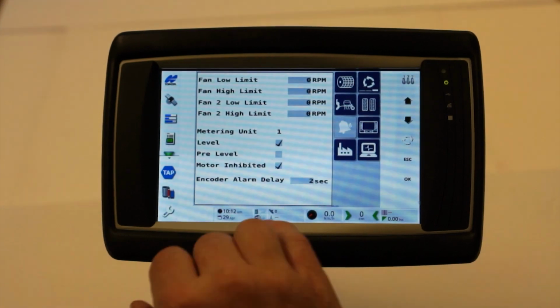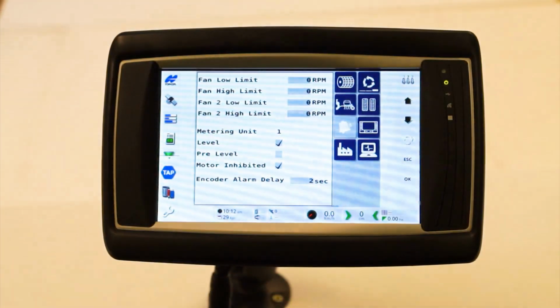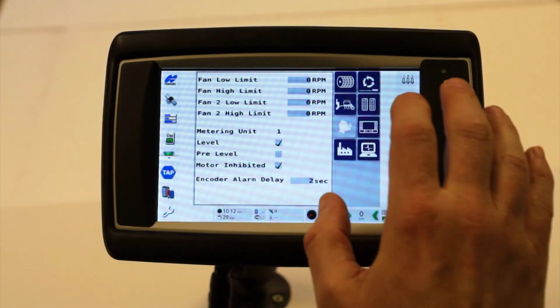The alarms page is set where you have motor inhibited, but all these fan speeds are turned off because we're measuring current, not RPM.